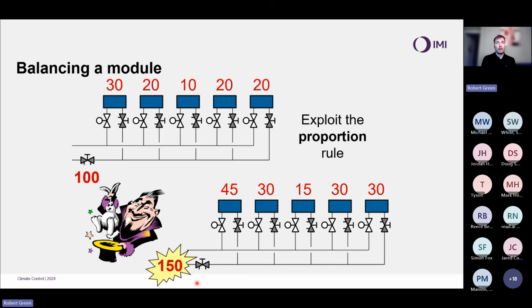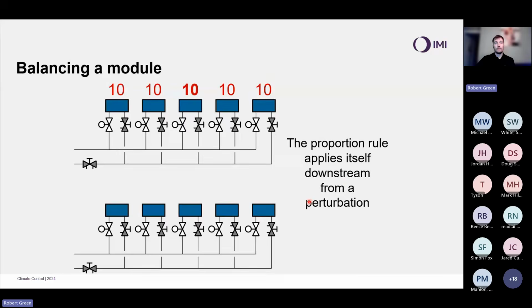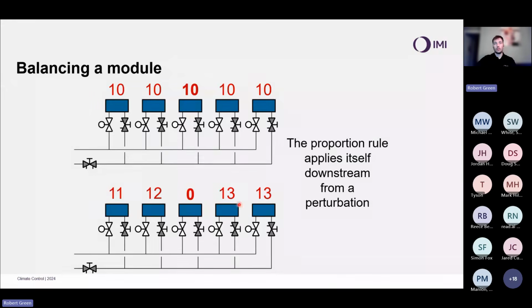Actually, it also applies itself downstream from a change. So if we take this again, this simple system here with 5 units, a flow of 10, let's say this is litres per second, pretty big system, 10 litres per second in each unit. If I shut this middle unit, downstream of this change I get the same proportional increase in flow on these two, but upstream, I don't get the same change. So what that is really useful for is that we can exploit this proportional rule when we're wanting to balance.